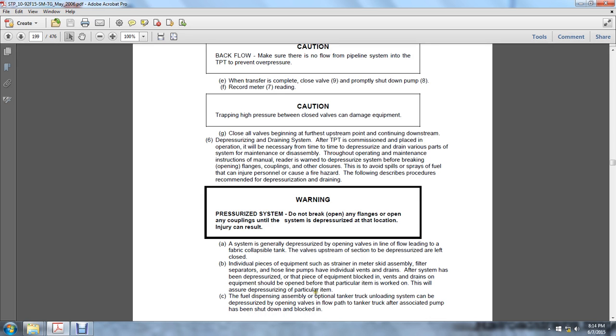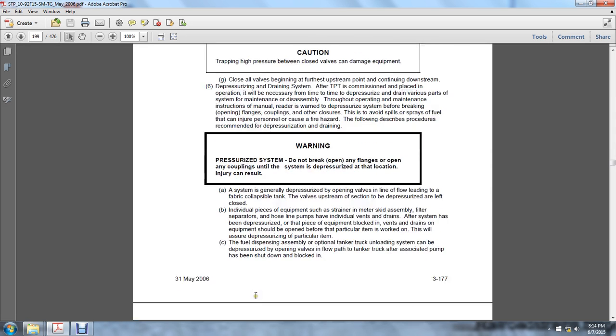The fuel dispensing assembly of the optional tanker truck unloading system can be depressurized by opening the valves in the flow path of the tanker truck, after the associated pump has been shut down and blocked in.